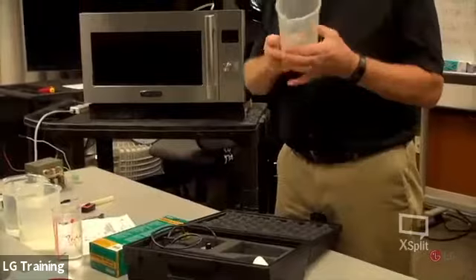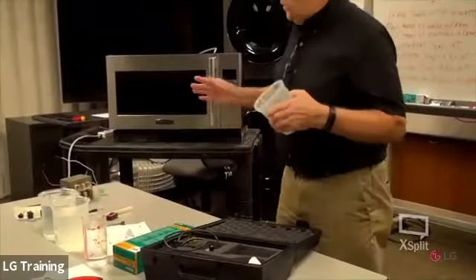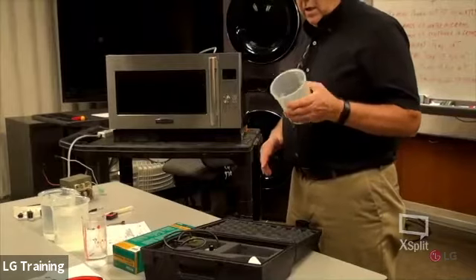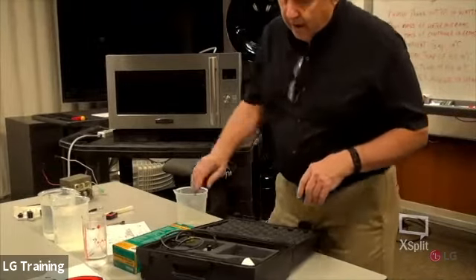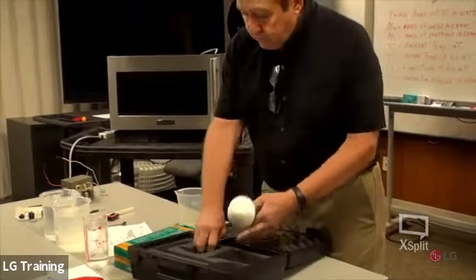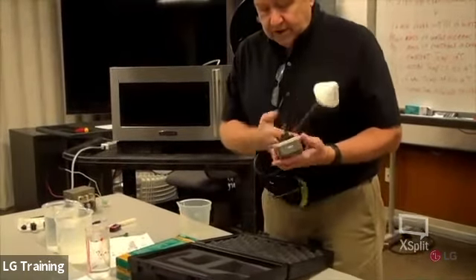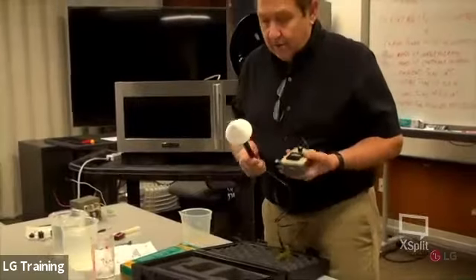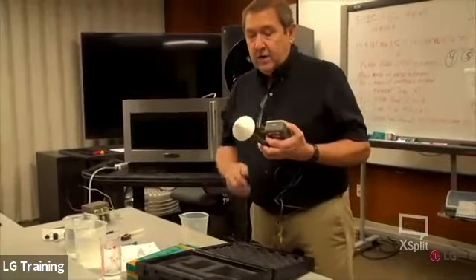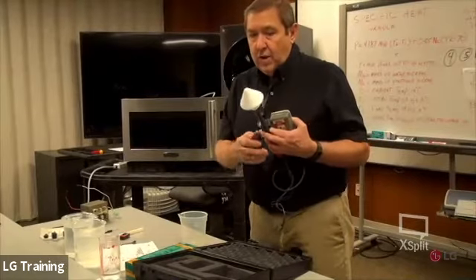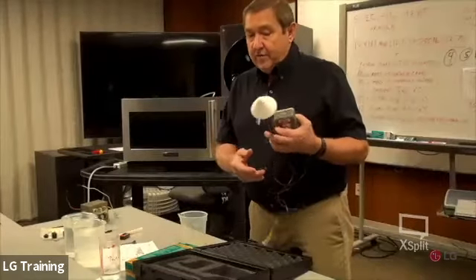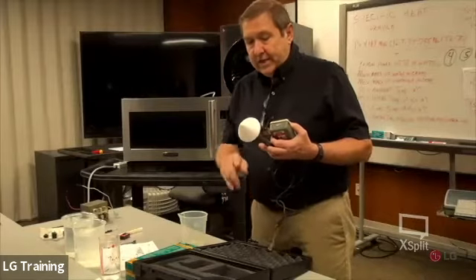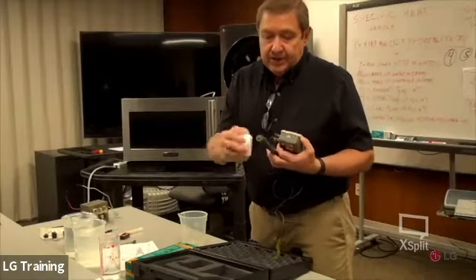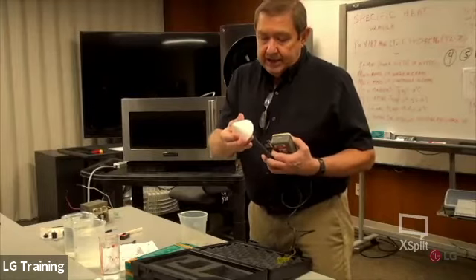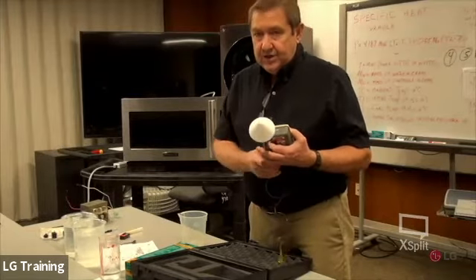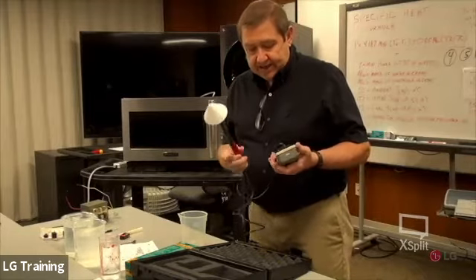When you're doing this check, it's required that you have a load in there. I'd say never operate the microwave without a load, always have something in there. Then you've got your meter here, this is just an analog meter. You've got this cone on it, and this cone needs to be on there, it's a spacer cone. It kind of looks like they did this to protect the microwave from scratching, but that's not the reasoning. It's a spacer because where we pick up that leakage has to be a certain distance when we're checking it, so this acts as that spacer.